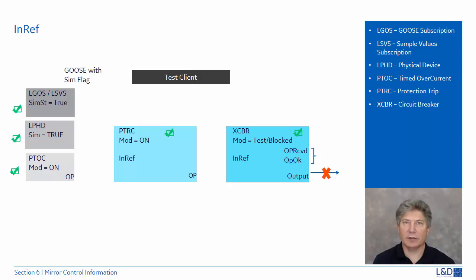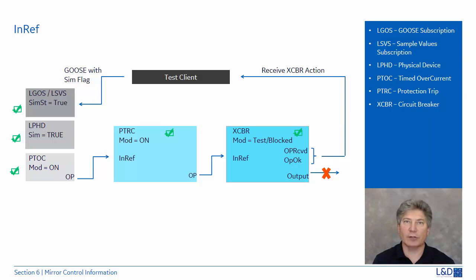Next, the test client sends a sampled value message with the simulation flag set. The signal is accepted, triggering a time overcurrent operate flag, triggering a trip condition operate flag, which in turn triggers the circuit breaker element to operate. The OP received and operate OK are returned back to the test client for validation. And this is all done while the IED is connected to the process. So this concludes this section on the mirror control information.